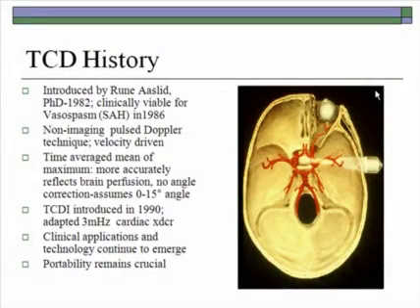Transcranial Doppler was introduced by Rune Aaslid in 1982 and clinically viable in 1986. It was first utilized for the evaluation of vasospasm following subarachnoid hemorrhage, and it is a non-imaging pulsed Doppler technique that is velocity driven. The velocities evaluated are the time average mean of the maximum, because Dr. Aaslid felt this more accurately reflected brain perfusion. There was no angle correction required, and an angle of insonation of 0 to 15 degrees is assumed.